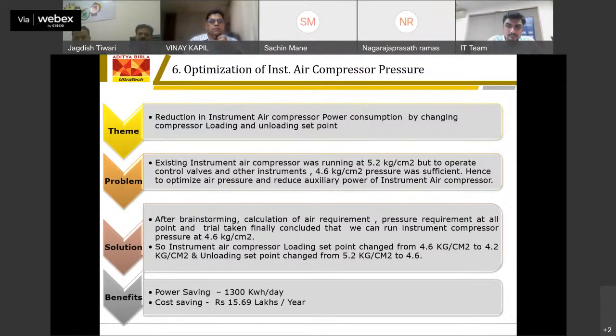This is also a process optimization in which we reduced our instrument compressor loading unloading pressure set point. Earlier it was 5.2 kg, and now we are operating at 4.2 kg per centimeter square, which also gives a saving of 1300 kWh, with 15.69 lakh in annual savings.